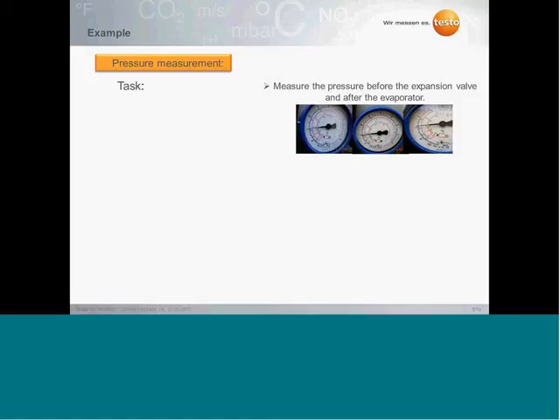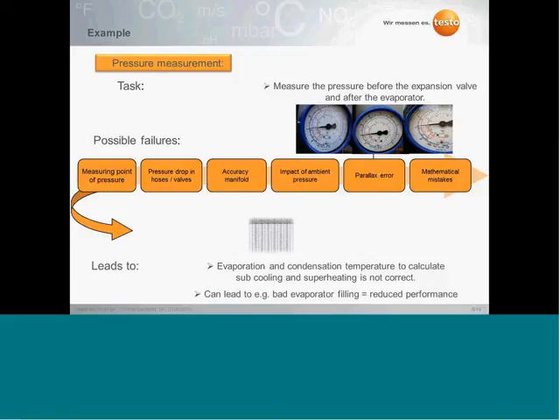First measurement: we have to measure the pressure before the expansion valve and after the evaporator. What are possible failures in this process? The first one is that the measuring point of pressure is sometimes not the point where we want to exactly determine the pressure. That means we cannot just determine the pressure in any place of the system. We have to check that we have a connection on the system where we can check the pressure. The second thing, which is not a very big failure point but still has to be considered, is that we can have a pressure drop in hoses, valves and the valve block of the measuring instruments. A major point is how accurate our manifold is.